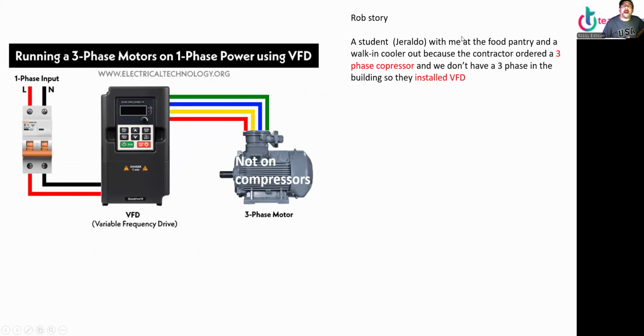Okay, so a student of mine, Geraldo, was with me at the food pantry, a customer I had for years, emergency housing. I worked for the homeless shelter. I had different locations, customers. And the walk-in cooler is out because the contractor ordered 3-phase compressors, but we don't have 3-phase power to the building. So they installed a variable frequency drive. Stupid. So we replaced the burned 3-phase with a single-phase 220 because it doesn't work.